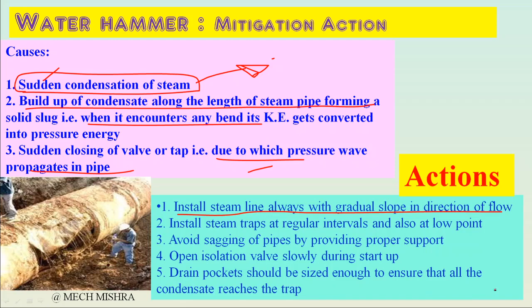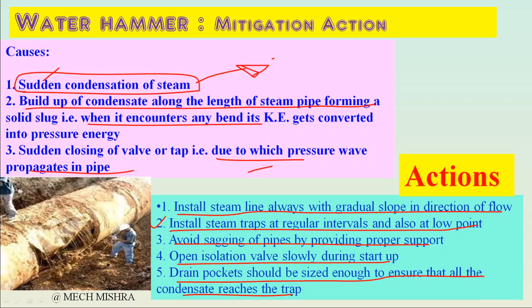Then open isolation valves slowly during startup, and drain pockets should be sized enough to ensure all the condensate reaches the trap. So these are the mitigation actions. We have to avoid the accumulation of the condensate. We have to provide the proper steam traps. We have to be cautious while opening and closing the isolation valves, which may give rise to the pressure wave. And the last one is installation of mechanical water shock arresters or surge tanks.